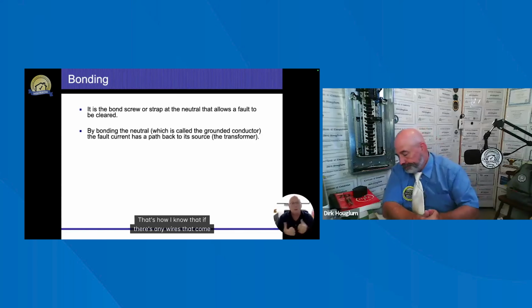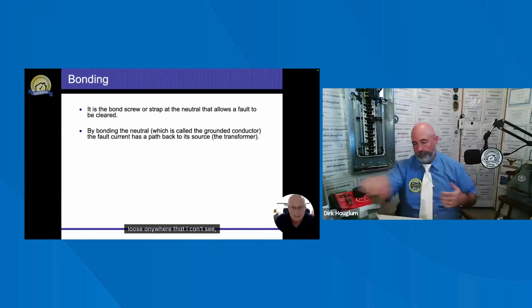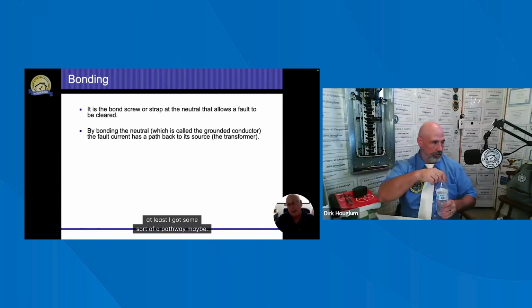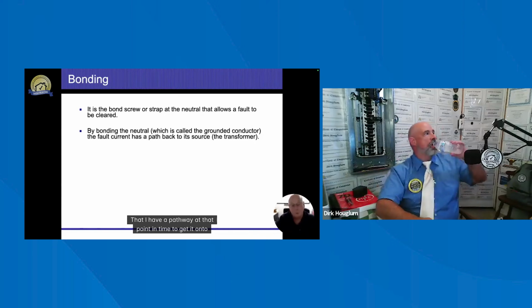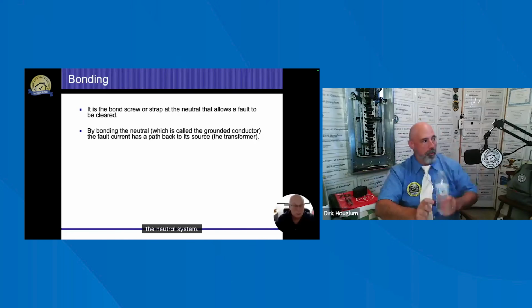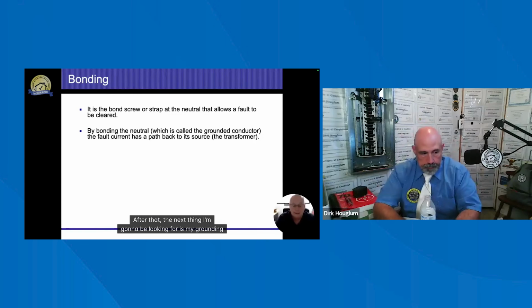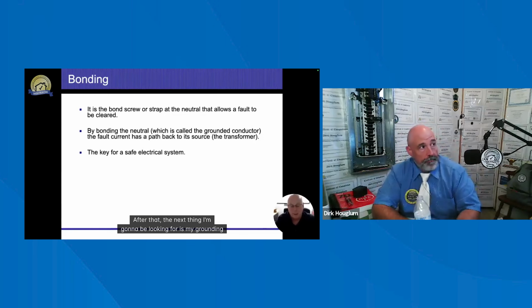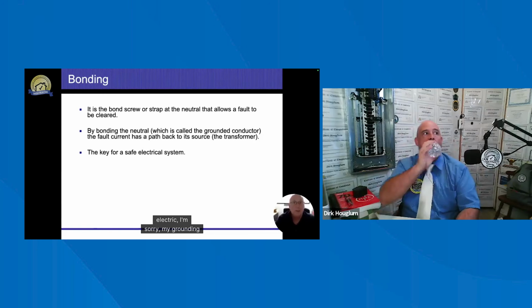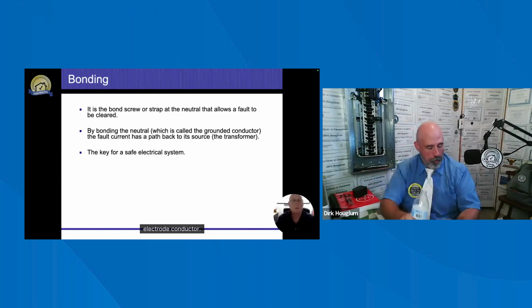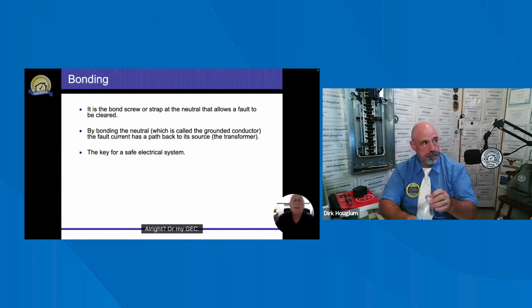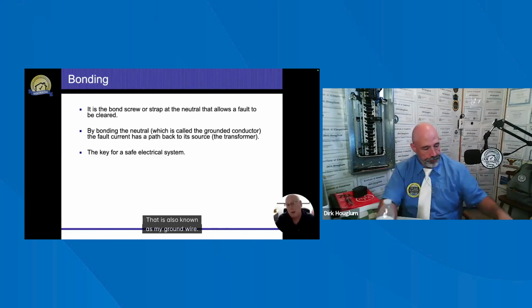That's how I know that if there are any wires that come loose anywhere that I can't see, at least I got some sort of a pathway, maybe. That I have a pathway at that point in time to get it onto the neutral system. After that, the next thing I'm going to be looking for is my grounding electrode conductor, all right, or my GEC. That is also known as my ground wire, but that's a specific ground wire, all right. That's going to go from the location where the bond is to wherever I'm going to be grounding this to.